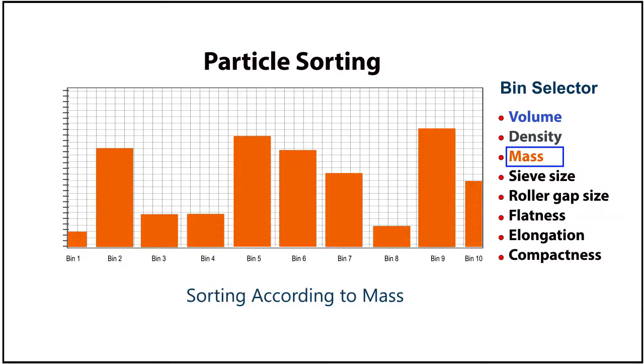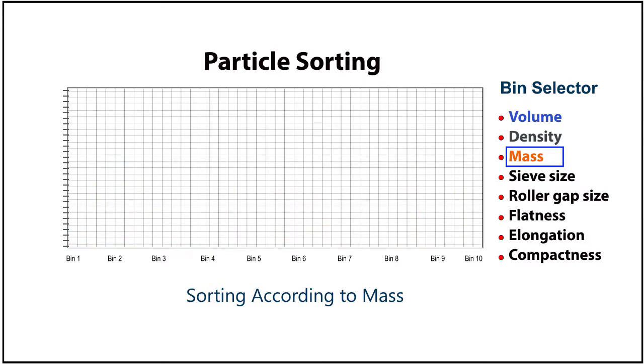Upper and lower limits can be set to ignore particles that fall outside the desired values. This will allow users to perform analyses on particles based on specific criteria, for example, chemical analysis on a specific density range, size or shape classification.